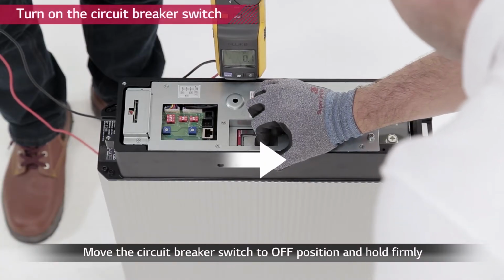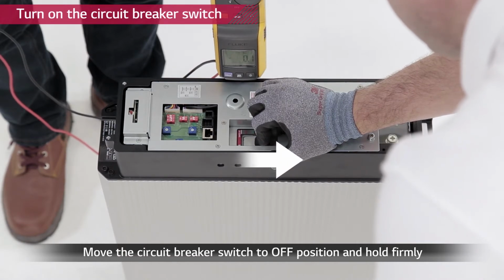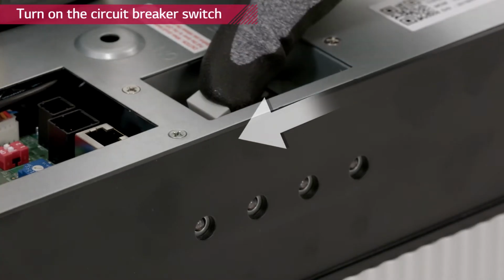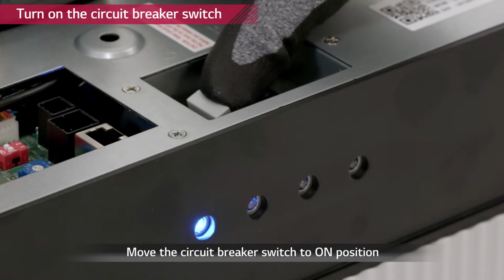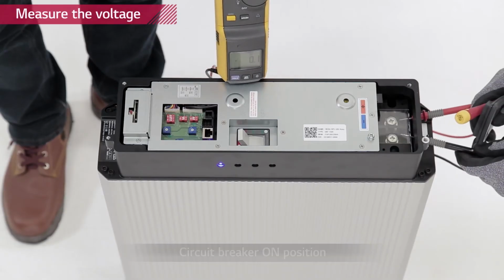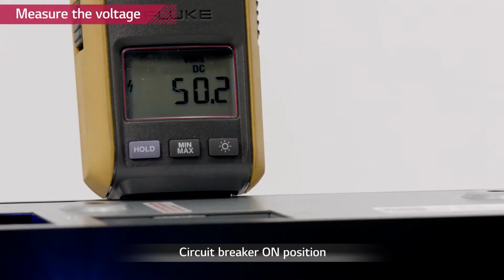Now, turn on the circuit breaker by moving the circuit breaker to off position first, then to on. Check the voltage level of the battery pack with a voltmeter. The battery pack has to have a minimum voltage of 38 volts.